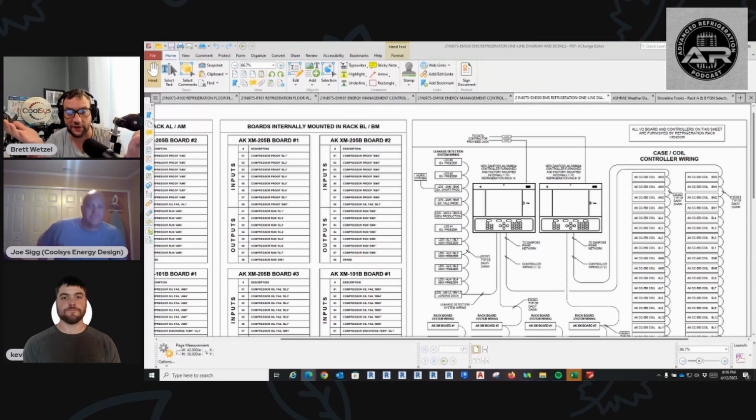Correct. The only reason why I said, if anyone's ever figured out the compression ratio, it's very low. It's like 3-to-1 on the one set of compressors and like 2-to-1 for the other. When I explain transcritical booster systems to people, it's usually upper level mechanics that I'm talking to, and I'm like, it's comparable to having a Carlyle compound compressor, right? Because you're basically taking the low temp and going through 2 cylinders, getting it up to that intermediate pressure, which is usually 68, 78 pounds, then goes in the back end of the Carlyle, and then comes out at whatever your ambient and your head pressure ends up being.